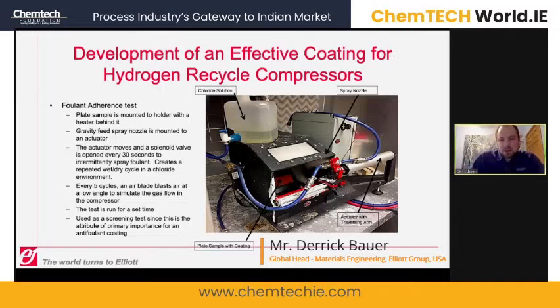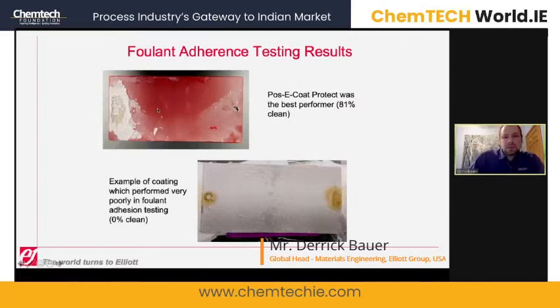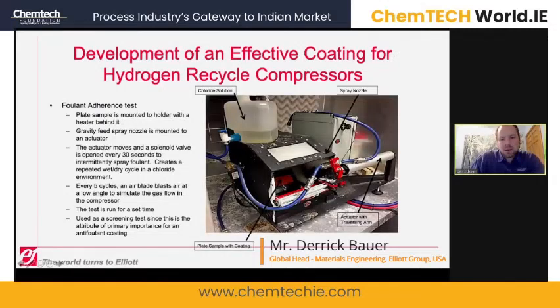So we tested a number of samples to see how the coatings would perform in this environment. A coating that was developed for this, that we call Pos-E-Coat Protect, performed very well in this test. I should mention, I'm sorry, I forgot to mention, this spray was applied every 30 seconds for a 24-hour period. And periodically in between the spray, an air blast was applied onto the coated sample, just in an attempt to blow the loose deposit off the coating sample. This was done in order to give a relative ranking for the propensity of a coating to release the ammonium chloride that was on the surface.